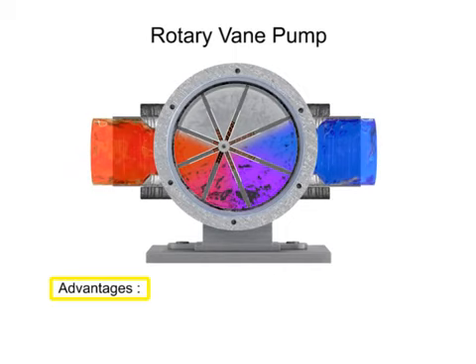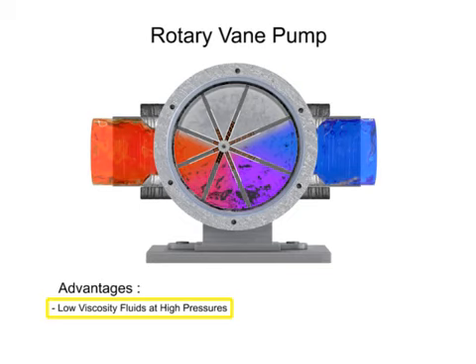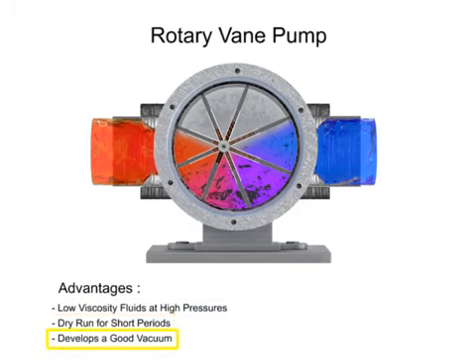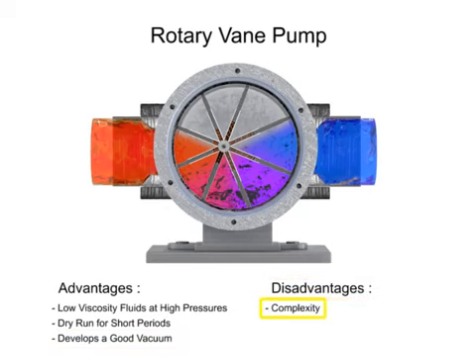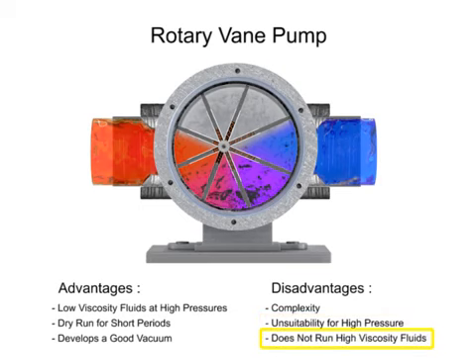The advantages of vane pumps are that they can handle low viscosity fluids at relatively higher pressures, can dry run for short periods, and develop a good vacuum. Their disadvantages include complexity and unsuitability for both high pressure and high viscosity fluids.